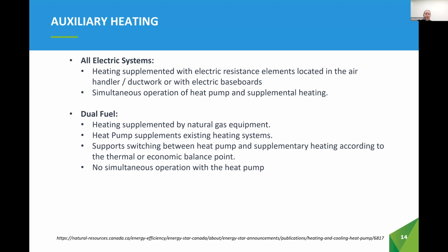In all electric systems, the electric resistance heating element is located downstream of the refrigerant coil, which typically results in topping up the supply air temperature when the outdoor air temperature is beyond the unit's thermal balance point. Dual fuel systems refer to air source heat pumps paired with natural gas heating equipment. Due to equipment arrangements, the heat pump and the gas furnace will not operate concurrently.